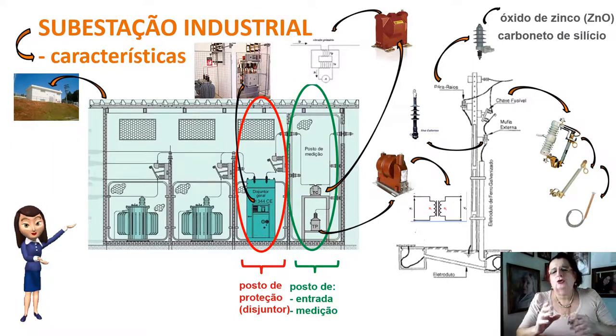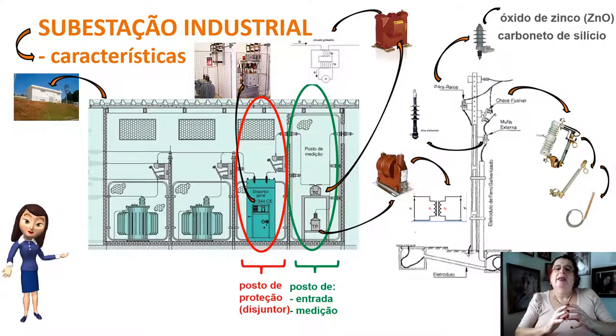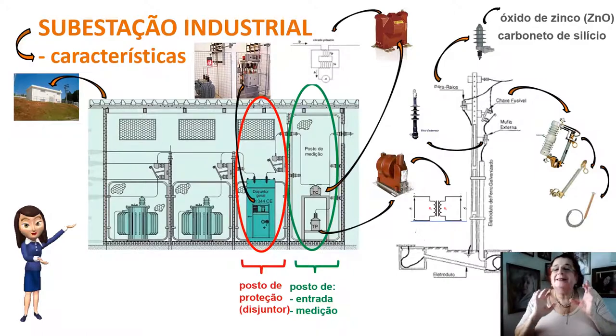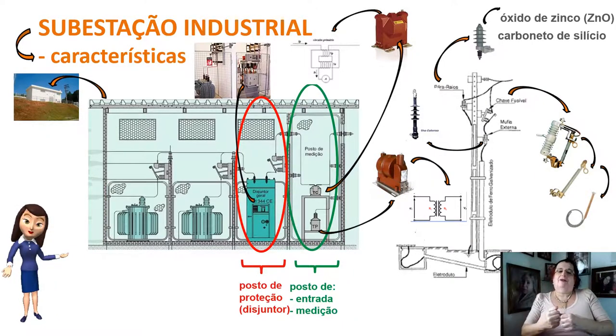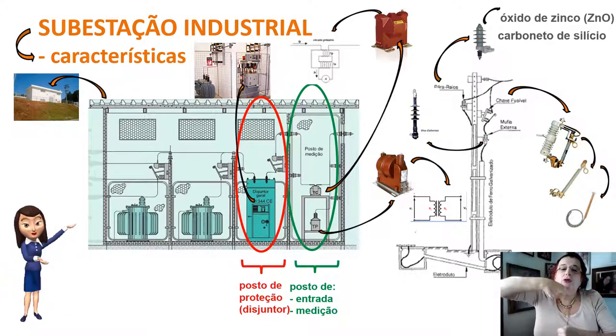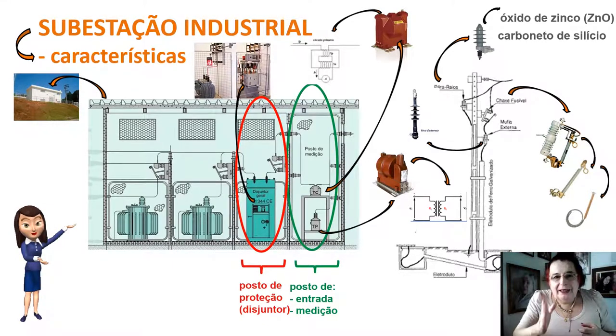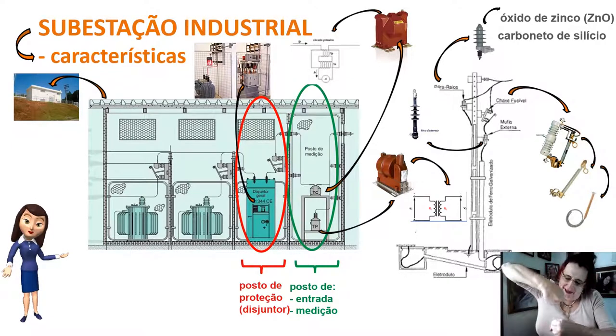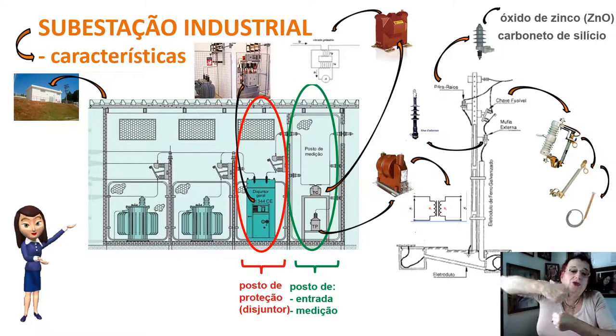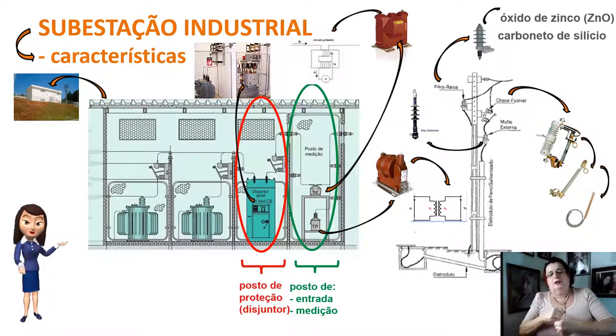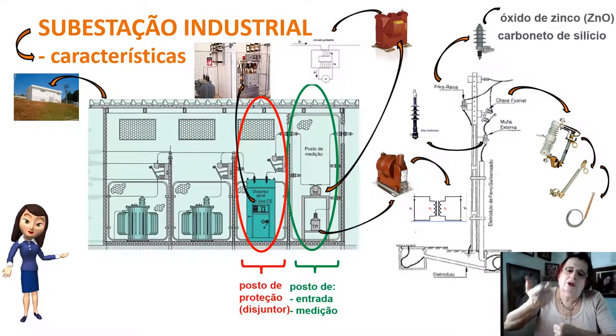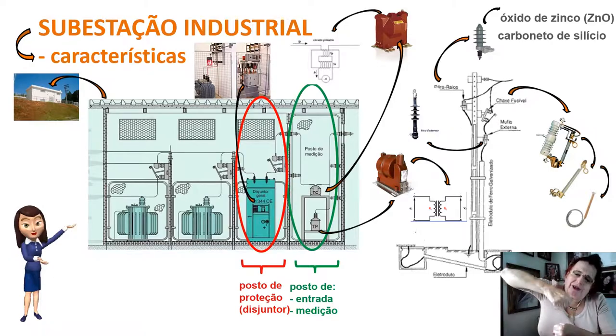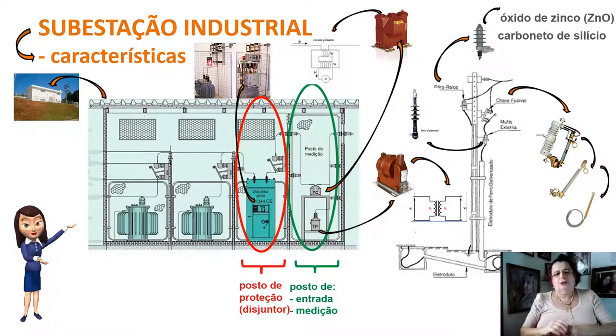É muito perigoso e é interessante sempre desligar todos os equipamentos de carga da fábrica antes de desligar o disjuntor, para que o centelhamento não seja muito elevado. Existem diversos tipos de disjuntores — a gás, a óleo — tudo para eliminar o centelhamento da abertura do disjuntor.